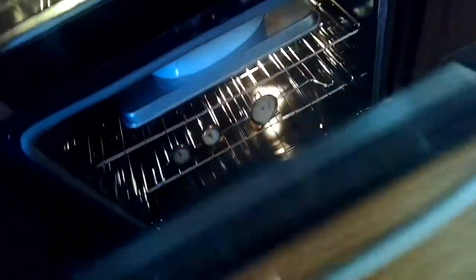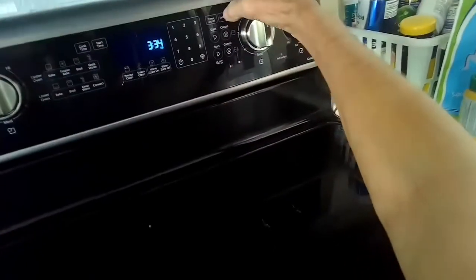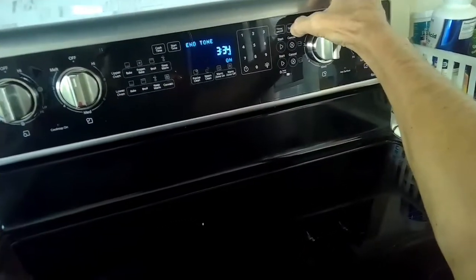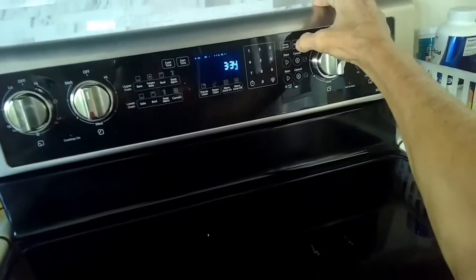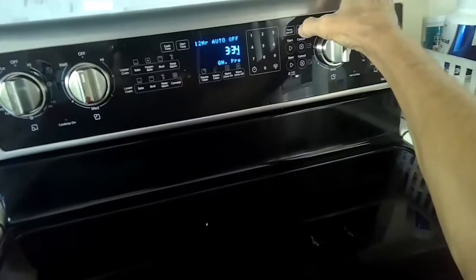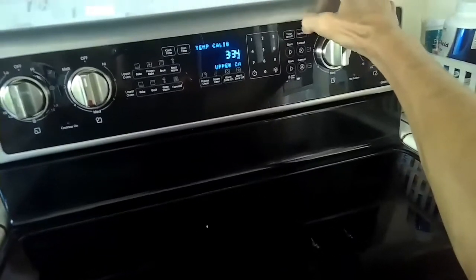We've got 3 analog ones going here, and they're all showing 300. So it's about 50 degrees off. Let's see how much we can tweak it to get a better reading. Yeah, they're all at 300. Okay, we're going to cancel that one. We're going to go to the settings button, press that until we get to calibration. There we go. Temperature calibration. I hit it, I think, about 12 times.